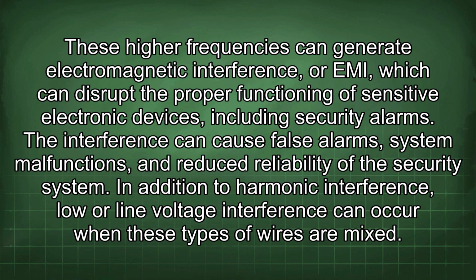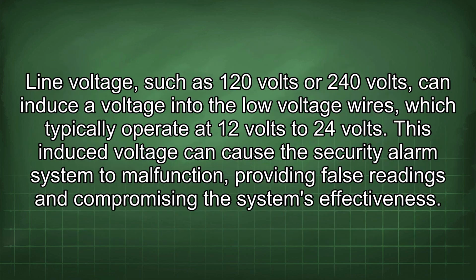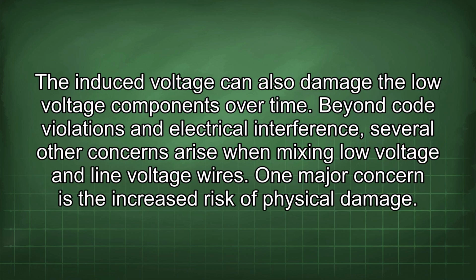In addition to harmonic interference, low or line voltage interference can occur when these types of wires are mixed. Line voltage, such as 120 volts or 240 volts, can induce a voltage into the low voltage wires, which typically operate at 12 volts to 24 volts. This induced voltage can cause the security alarm system to malfunction, providing false readings and compromising the system's effectiveness. The induced voltage can also damage the low voltage components over time.